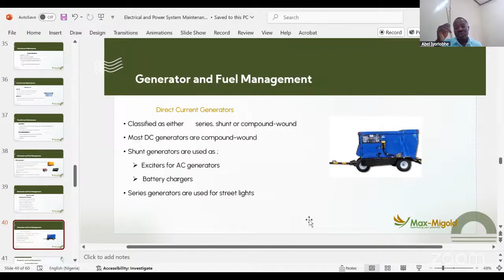Selection of generator: determine the sum total, like that man said when we started, determine the sum total of the load in your building. Let's say the total sum of your load is 40 kilowatts. You have 4 air conditioners of 10 kilowatts. What you need to do is aggregate this equipment together and divide it by 0.5 to give you the size of the generator that you want. Can somebody do that for us? So let's just do it now.